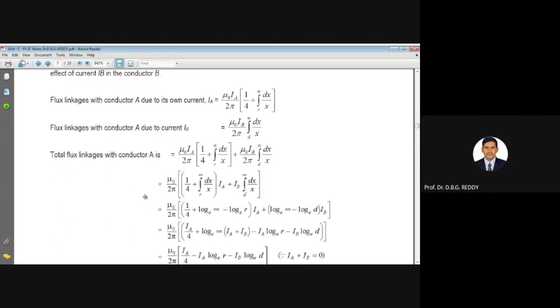Now add both these equations, simplify, substitute the limits, and use the relation IA plus IB is equal to 0. You can keep everything in terms of IA or IB, no problem: IA is equal to minus IB, or IB is equal to minus IA. Using that relation, you finally get mu naught IA by 2 pi times (1 by 4 plus log E base d by r) Weber turns per meter. We are calculating the inductance of the transmission line per meter. If it is per kilometer, multiply by 1000, since 1 kilometer is equal to 1000 meters.